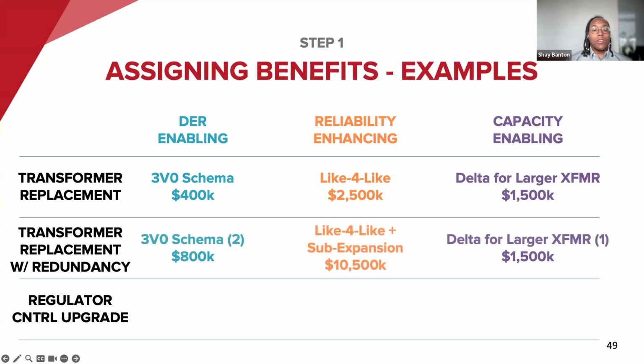On the next slide you see those costs split again. Like for like still goes to reliability. Substation expansion is probably necessary to accommodate that second transformer, that's a lot. However, the benefit that DERs get from this, which is actually increasing the capacity of this particular substation in general, is just the delta above the like for like value.